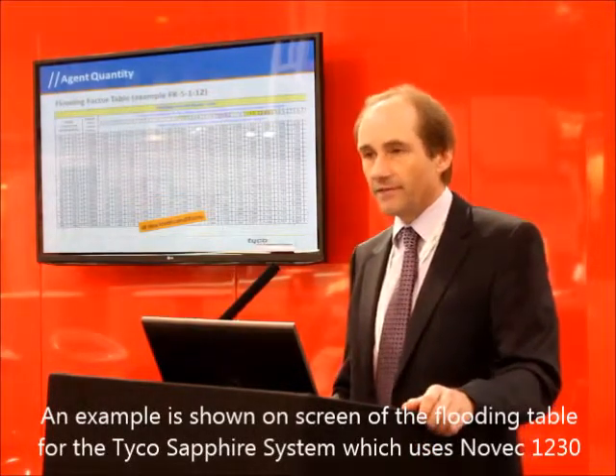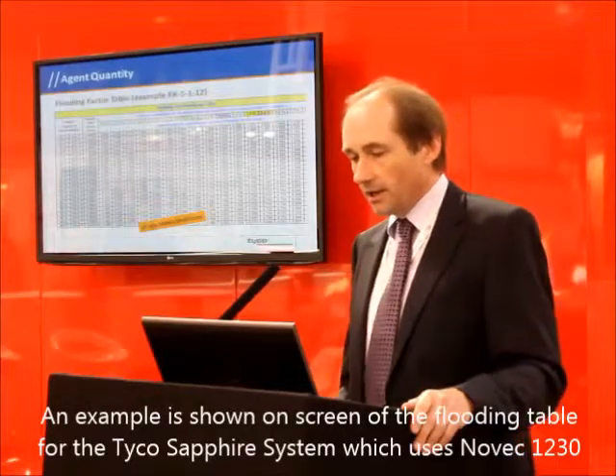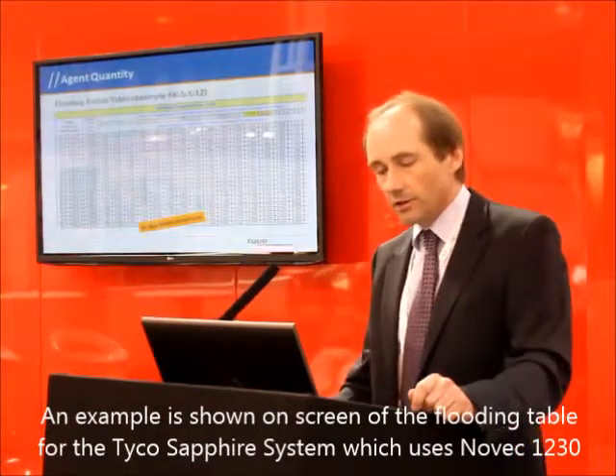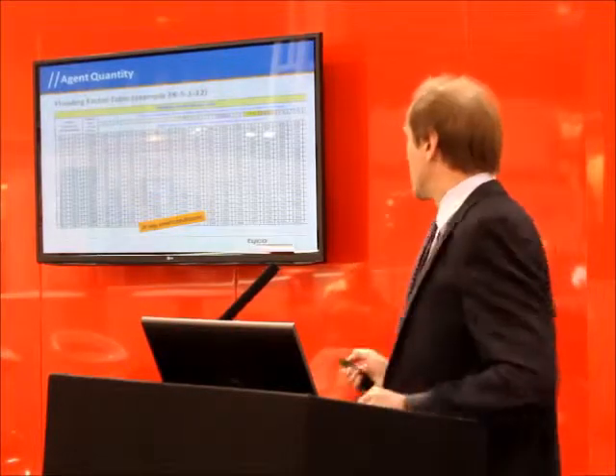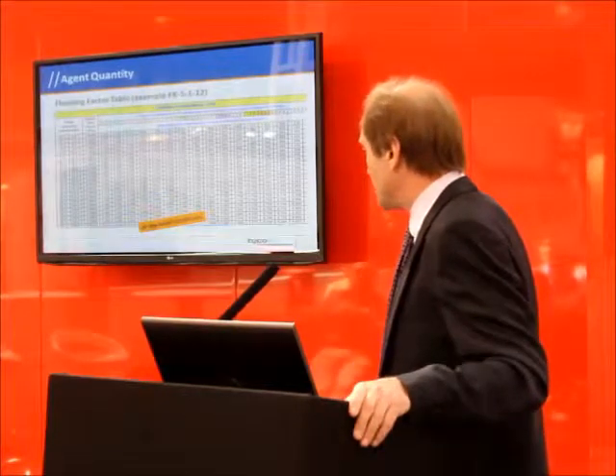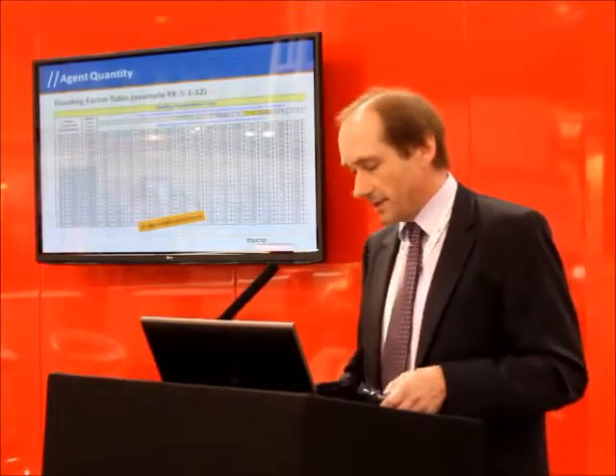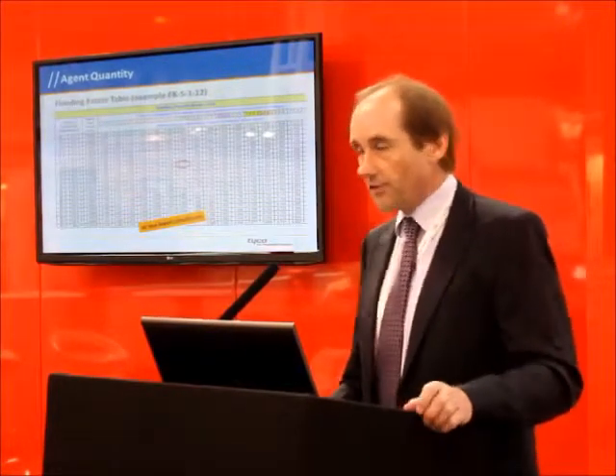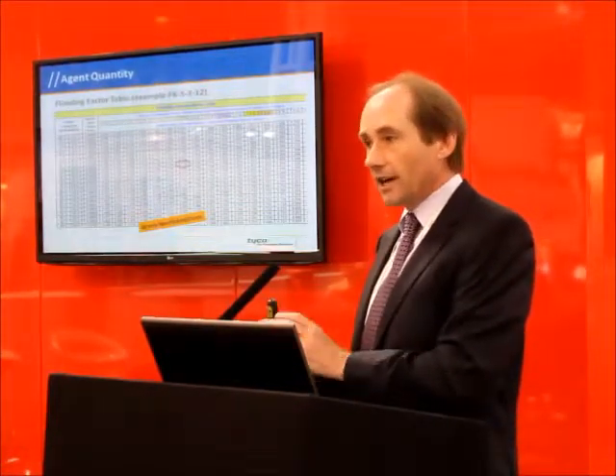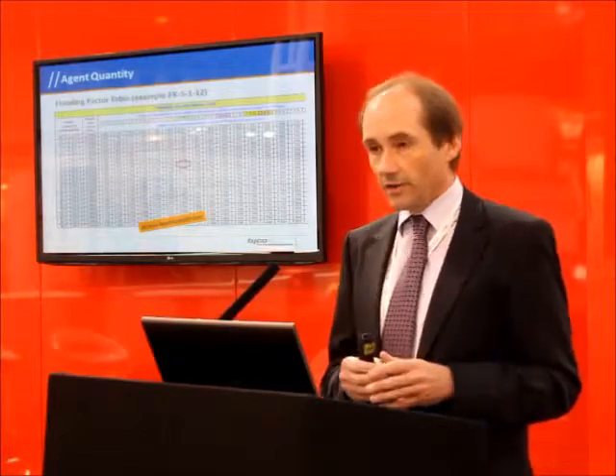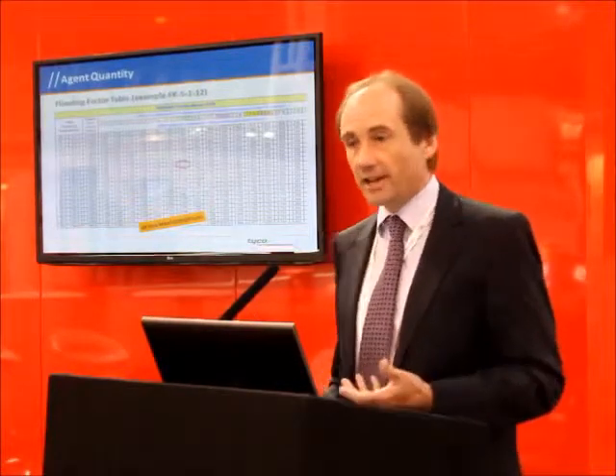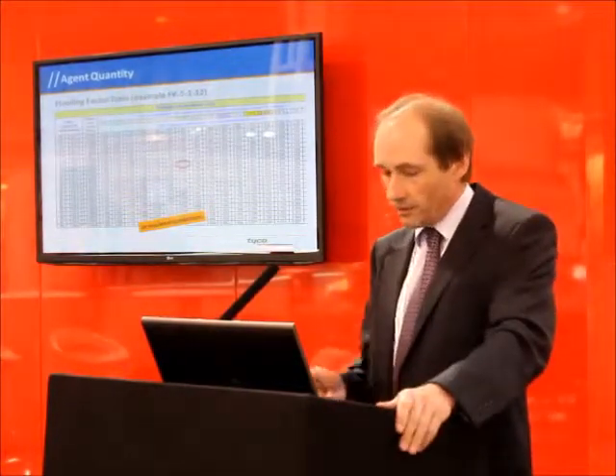This example is for FK-5-1-12, otherwise known as NOVEC 1230, or to give a plug for the Tyco system, the Sapphire system. What you do is look at the concentration that you require. So if we're looking at a concentration of 5.3%, which is in accordance with the European standard, at a minimum design temperature of 20°C, you would see that you need a flooding factor of 0.779. So you take the volume, multiply it by 0.779, and that gives you the number of kilograms. So 100 cubic metres multiplied by 0.779 means that you need 78 kilograms of NOVEC 1230 — of course, at sea level conditions.